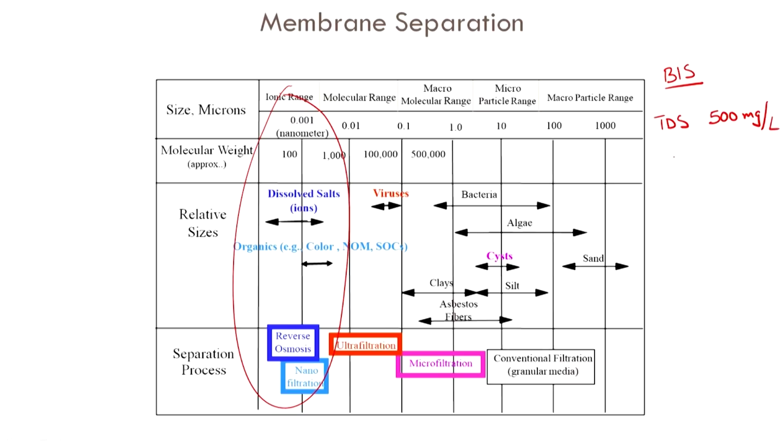And typically in RO systems with the bypass, little to no TDS, almost 0 TDS, comes out here. Not 0, it is almost 0. And so that is why they bypass it and mix it here, such that the mixture will be, let us say, 50 or 100 and so on, depending on what the poorly knowledgeable consumer asks the person to fit in, right. That is the amount of bypass that people are talking about.